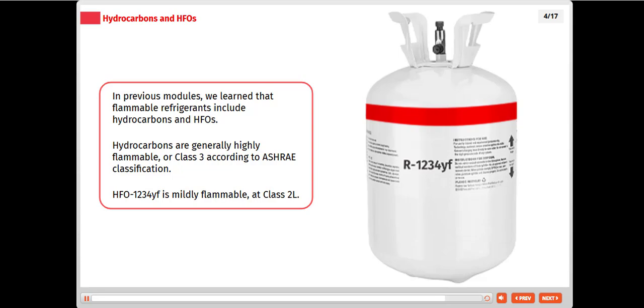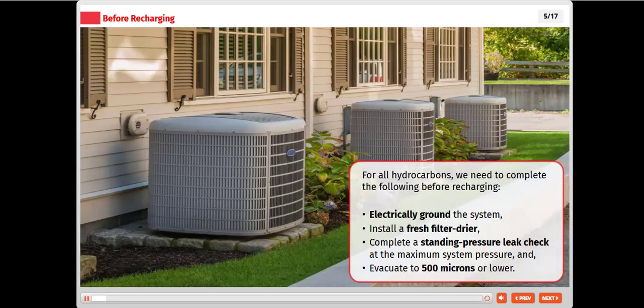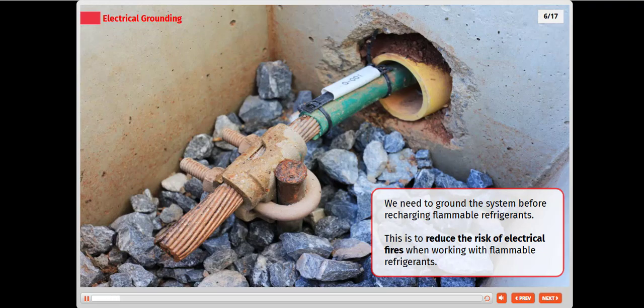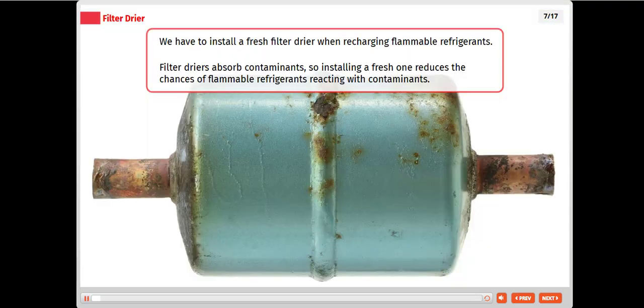For all hydrocarbons, we need to complete the following before recharging: electrically ground the system, install a fresh filter dryer, complete a standing pressure leak check at the maximum system pressure, and evacuate to 500 microns or lower. We need to ground the system before recharging flammable refrigerants. This is to reduce the risk of electrical fires when working with flammable refrigerants. We have to install a fresh filter dryer when recharging flammable refrigerants. Filter dryers absorb contaminants, so installing a fresh one reduces the chances of flammable refrigerants reacting with contaminants.